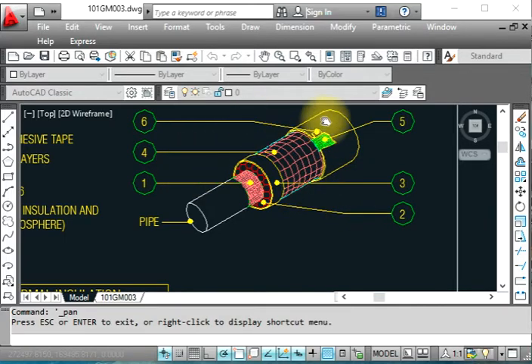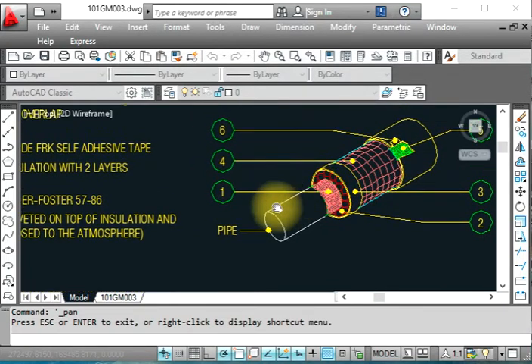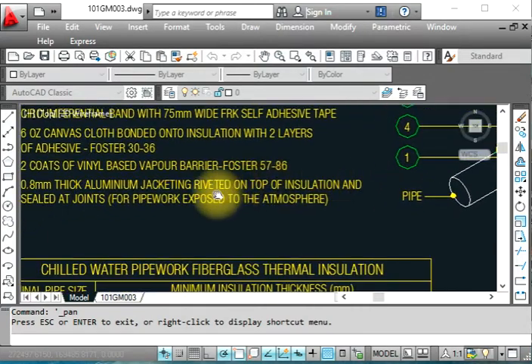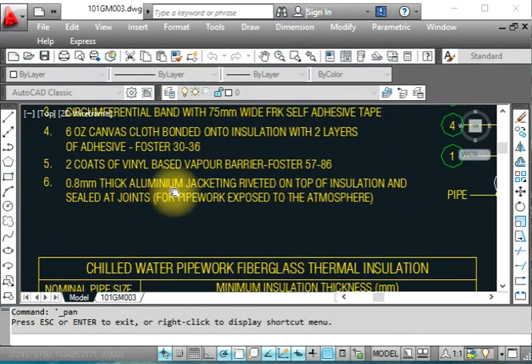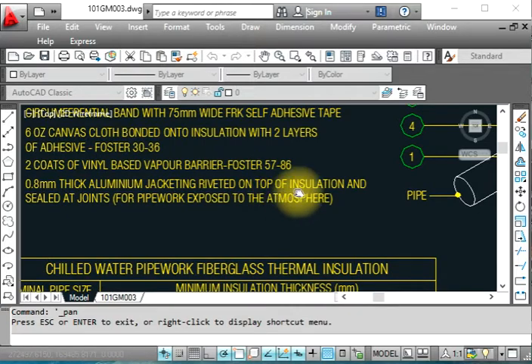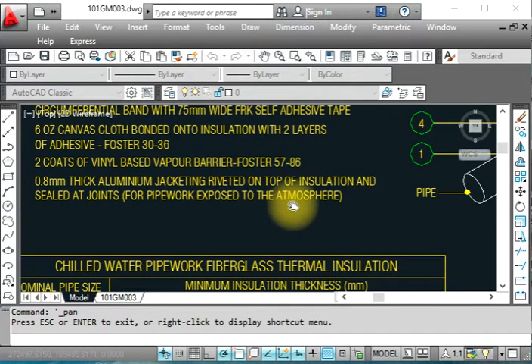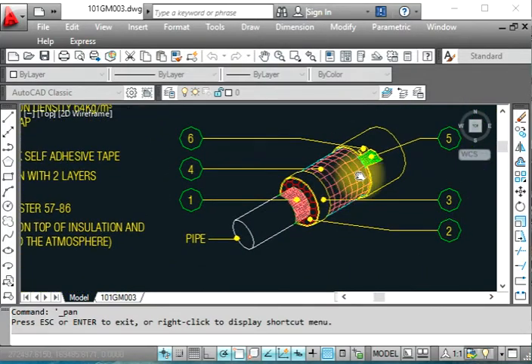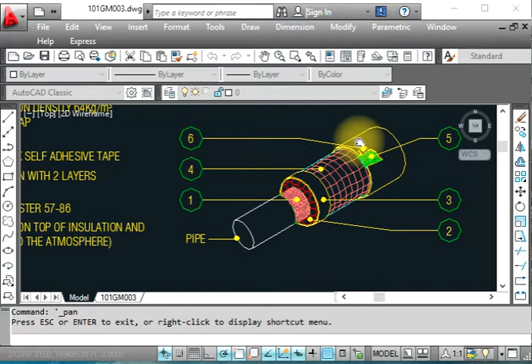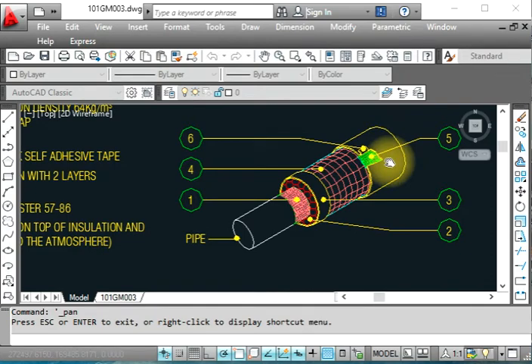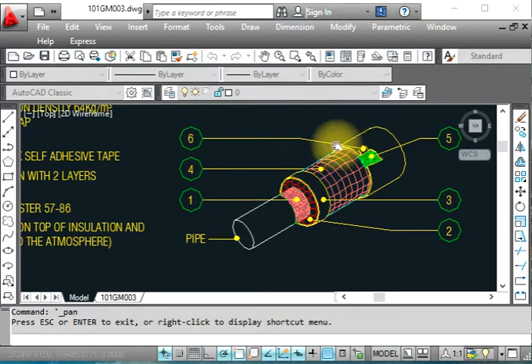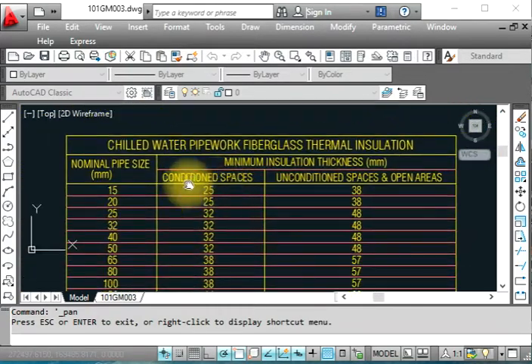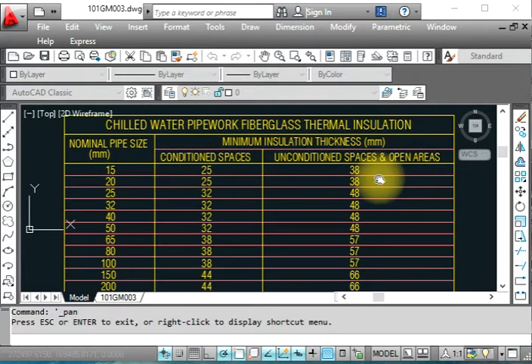Number six is for exposed areas. We put aluminum cladding. This is aluminum jacketing riveted and sealed at joints for pipework exposed to the atmosphere. When the pipe is exposed to the sun, we have to put this. Inside the room, parking area, office area, above the ceiling, or under the roof, there is no need for aluminum cladding. But if it's outside exposed to the sun, you will provide this aluminum cladding.